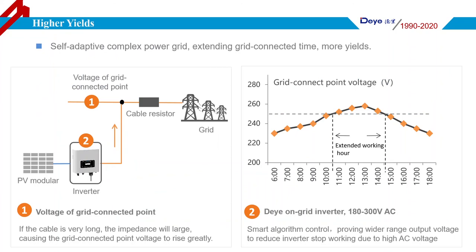If the power distribution cable is very long, the cable impedance will increase, causing the grid connection point voltage to rise greatly. For example, in rural areas of India and Pakistan where the grid is very unstable, inverters need a wide range of output voltage to handle these conditions.